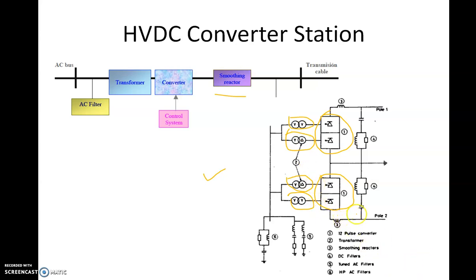Then we have something called a smoothing reactor. Smoothing reactors are kept immediately after the converters, once the power is converted to DC. You can see all the components shown here are in pairs. If there is a converter here, there is another one. If there is a smoothing reactor here, there is another smoothing reactor. These are in pairs because we are working on two lines or two poles — pole one and pole two.